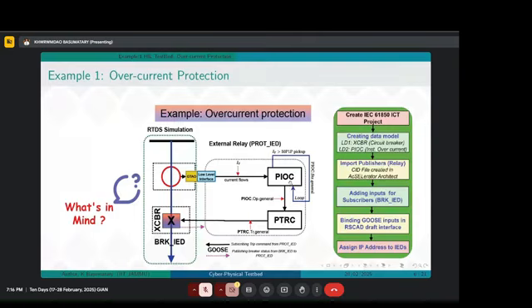And if I would like to trigger the relay, then I should have these logical nodes in my data sets. So PIOC.Str, meaning start general, will always check whether this threshold is exceeded or not. If it is exceeded, then it will issue a protection trip condition. It will send a condition signal to the PTRC.